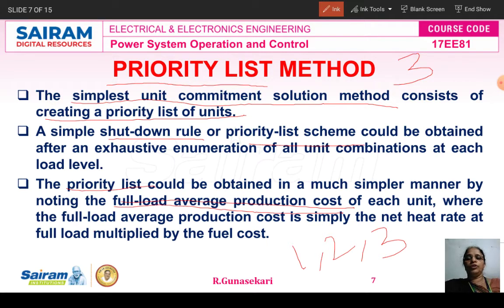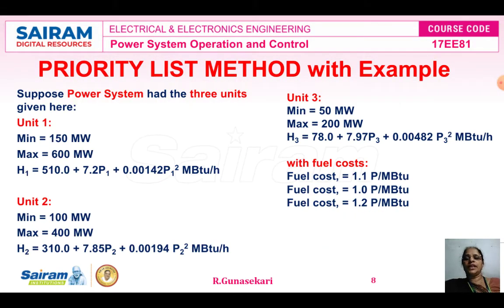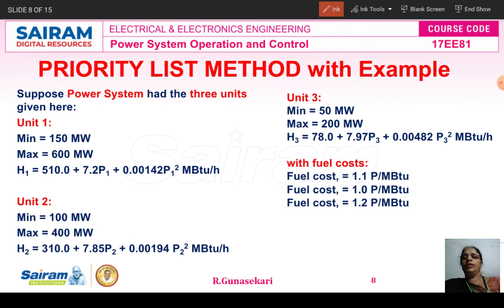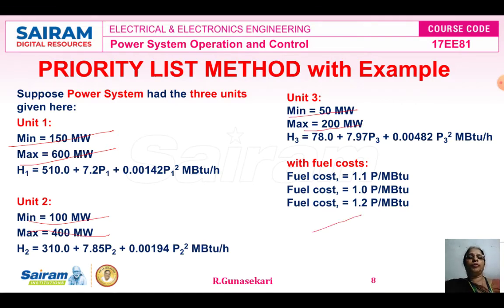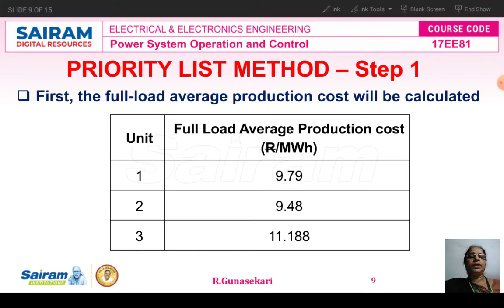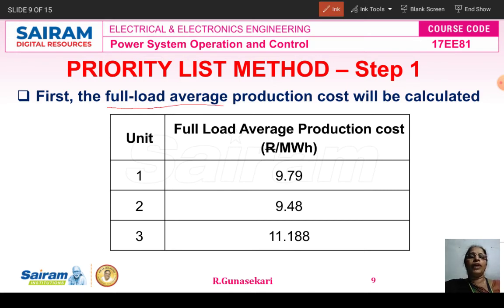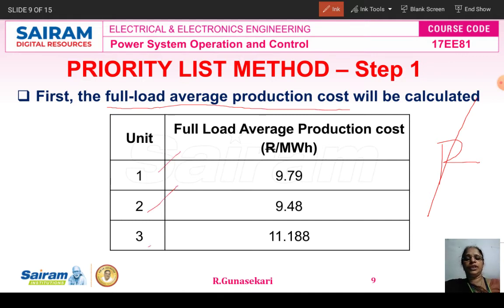What are the steps followed for the priority list method? The first step is to calculate the full load average production cost in units of $/MWh. The full load average production cost is the net heat rate at full load multiplied by the fuel cost. For unit one: 9.79, for unit two: 9.48, for unit three: 11.188. First step is complete.